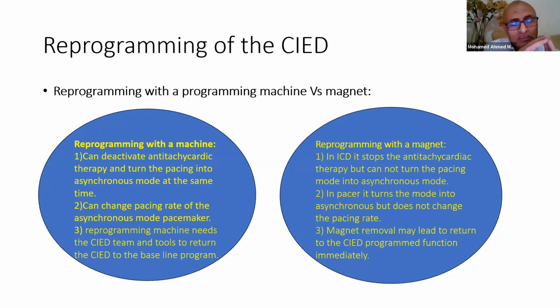What is the case if we have a pacemaker? If we have a pacemaker, the reprogramming machine can convert the pacemaker from the synchronous mode to the asynchronous mode. And also it can increase the pacing rate. If the pacing of the pacemaker in asynchronous mode is 60, it can increase it to 80, to 90, up to the rate that is suitable for the perioperative period. If we apply a magnet on a pacemaker, it will convert the mode from synchronous to asynchronous pacing, but it will not do anything with the pacing rate. If the default rate in asynchronous mode of this device is 60, it cannot increase. The magnet cannot increase the pacing rate. So the magnet has a limited effect on the device compared with reprogramming with a reprogramming machine.